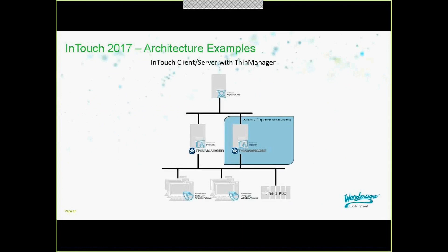In an InTouch client-server type architecture, we have two InTouch nodes — one primary and one secondary, or a redundant server — based on a tag server concept. We would have an application running in the console session or on the server itself in RDS or non-RDS environments, and our client machines gather data from that tag server. If there was a failure, data acquisition, alarming, historical logging would switch to tag server two. However, that's not completely built-in functionality — some scripting or engineered solution in the background is required.